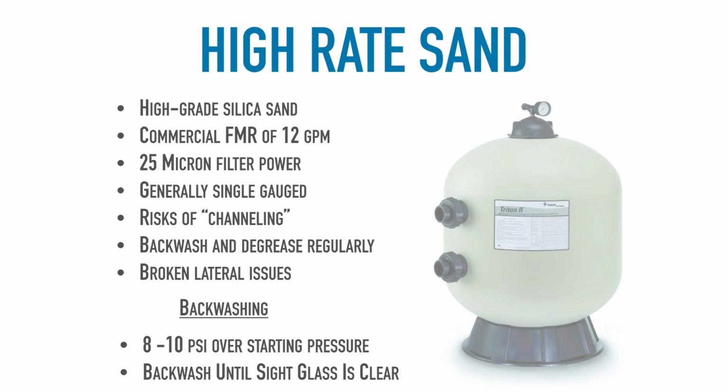Now, the starting pressure is either what you started that filter out at brand new, or after a fresh backwash or cleaning of that filter. When that starting pressure raises 8 to 10 psi over start, we know that we need to re-backwash. We need to clean that filter out. So really quickly, turn over to page 144 in your books.